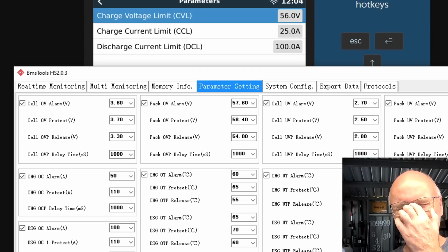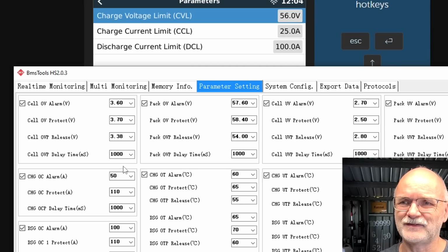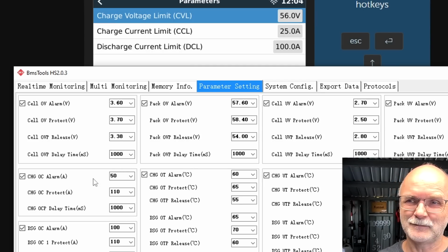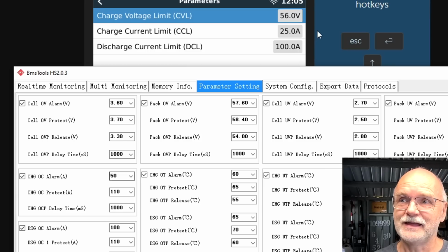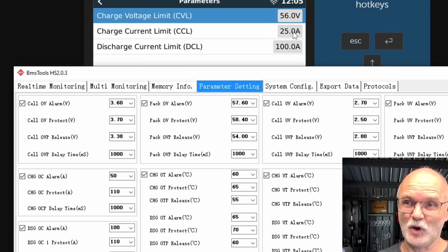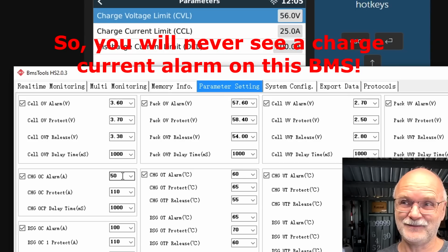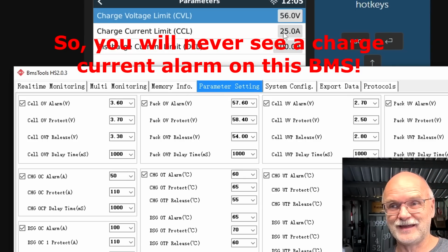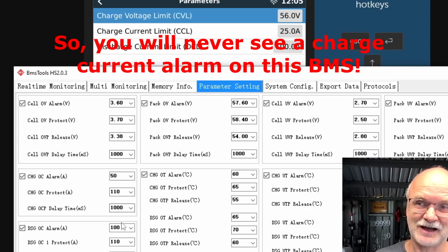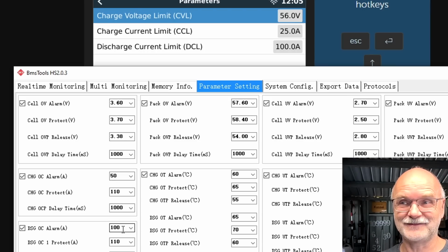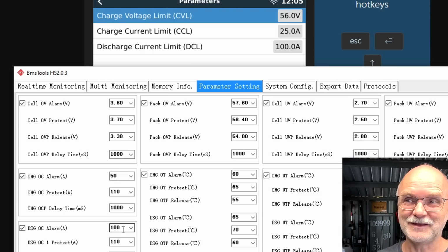So this is a bit of a stupid thing with this BMS here. You have to set the alarm twice as high as the actual desired charge current from your inverter. This sits on 50 amps and it charges only with 25 amps, but the discharge is exactly the same as the discharge limit. So this logic makes no sense to me.